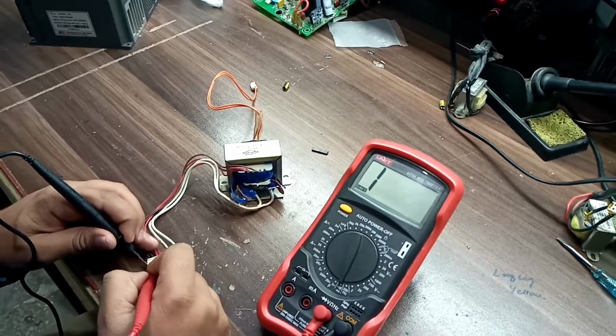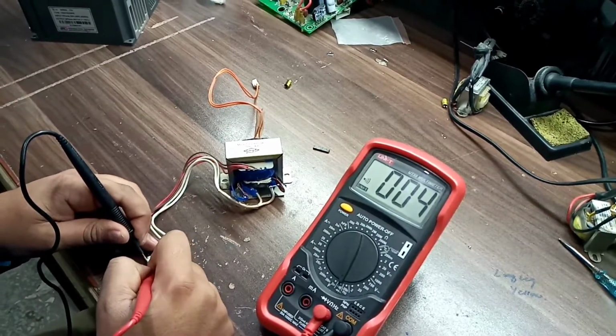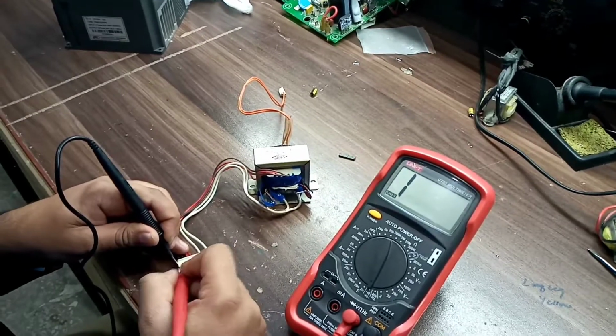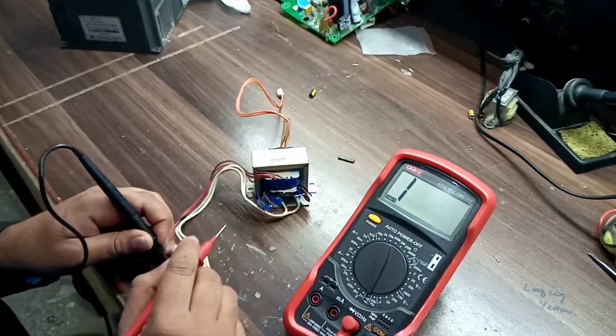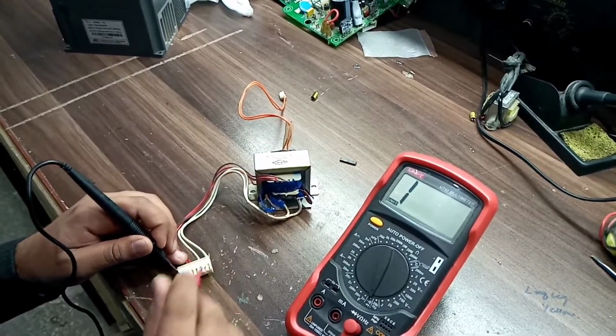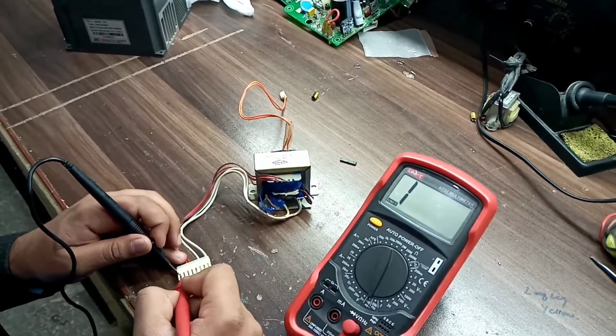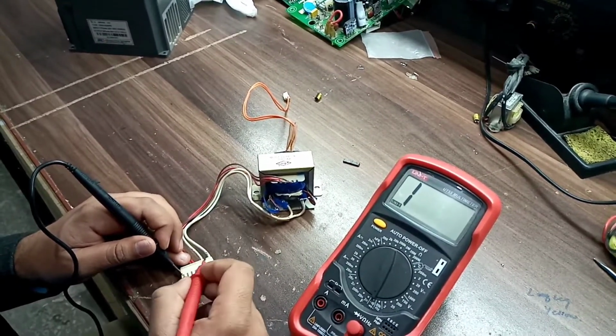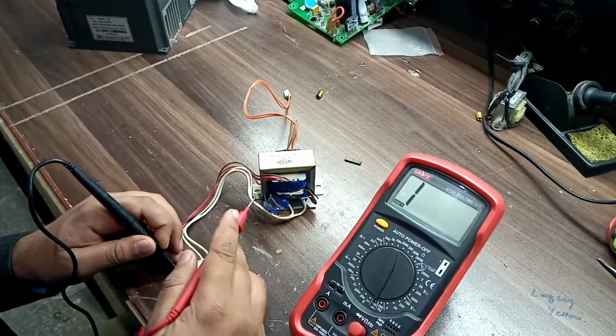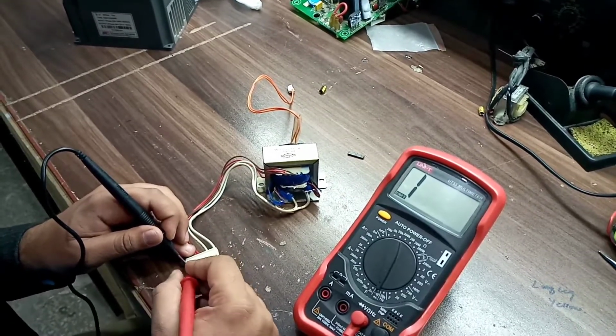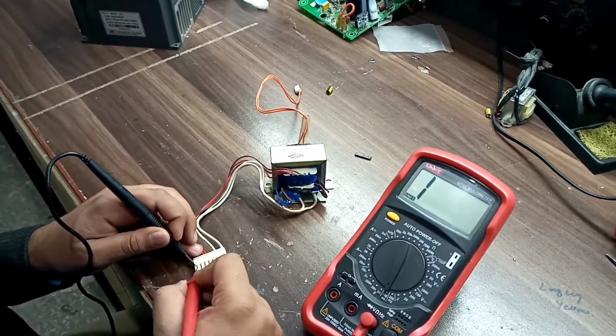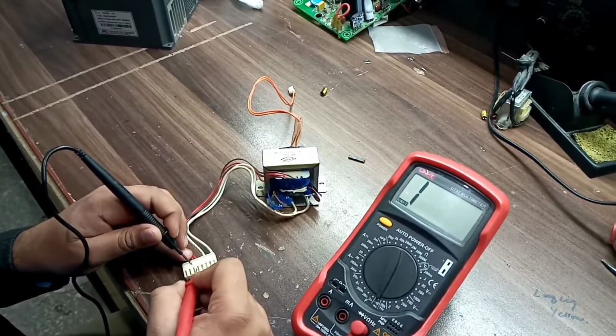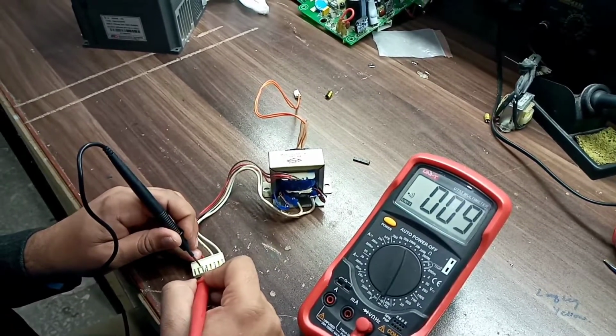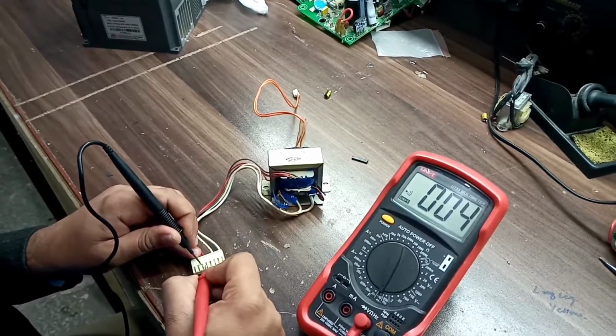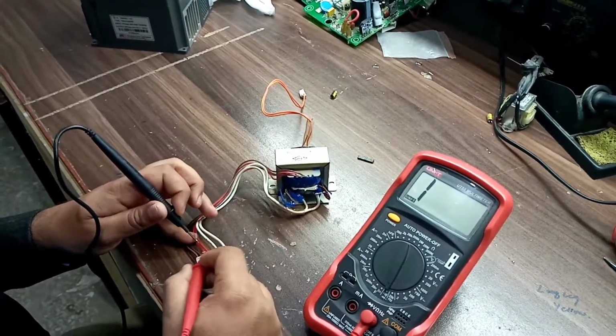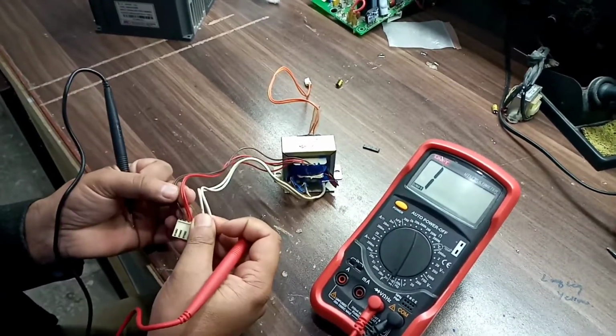Here's the brown pair, and it's giving us sound. In the transformer coils, whenever we place it on continuity and check the windings, it should always give you sound, meaning it's internally okay and the circuit is not open. The red pair is also okay.